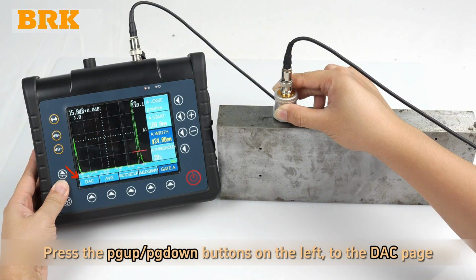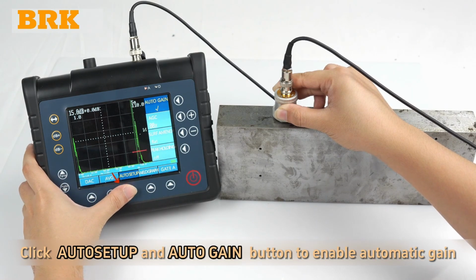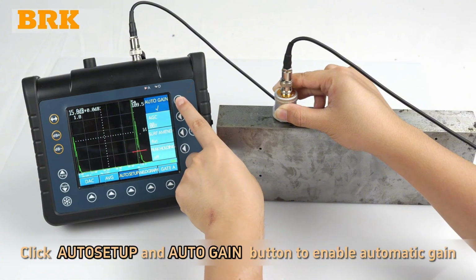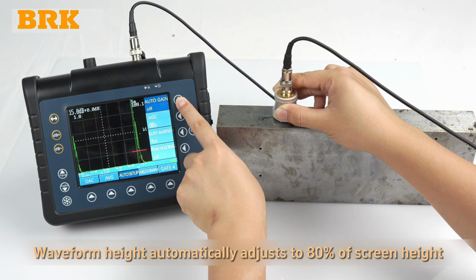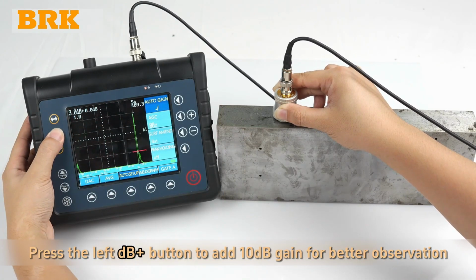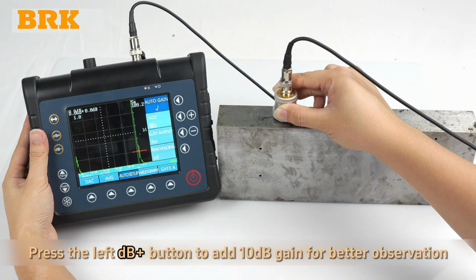Press the page up or page down buttons on the left to the DAC page. Click Auto Setup and Auto Gain button to enable automatic gain. Waveform height automatically adjusts to 80% of screen height. Press the left dB plus button to add 10 dB gain for better observation.